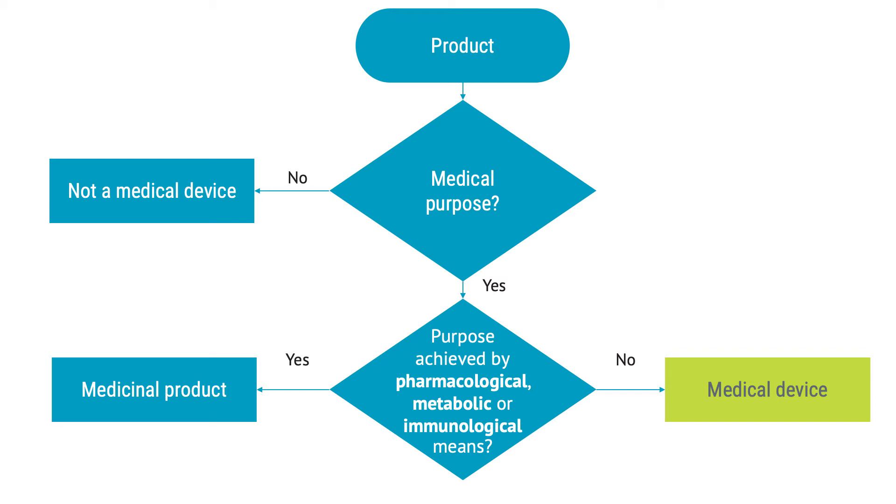And if it is a medicinal product, there are other norms that regulate your product. I've used the words 'likely to be a medical device' and 'likely to be a medicinal product' — why do I say that? Well, sometimes it's not entirely clear what kind of classification your product should have. Some might say that it's a medical device and others say that it's a medicinal product, or is it maybe neither of the two? Being the responsible manufacturer, you need to make up your mind what you think and document your rationale for that opinion. If it's hard to decide, it could end up being a competent authority that ultimately decides for you how your product should be classified. Luckily, for most products it is not that hard to crack from a classification point of view, but this is a heads up for those who think they might have a borderline product.